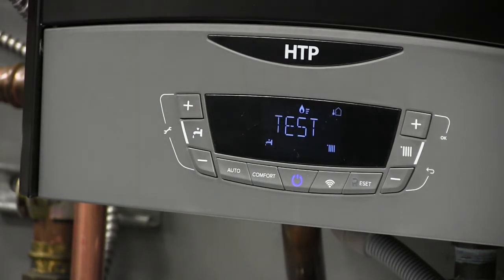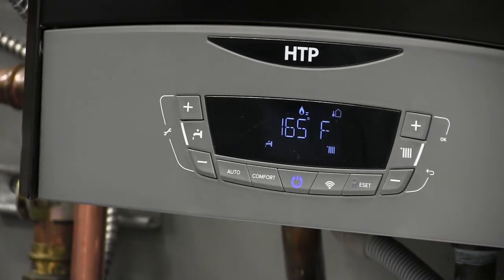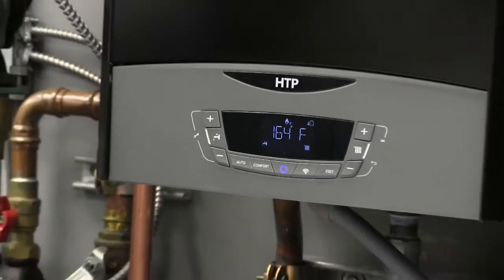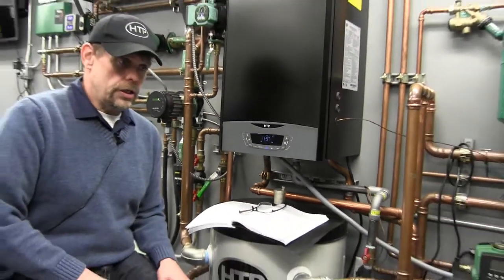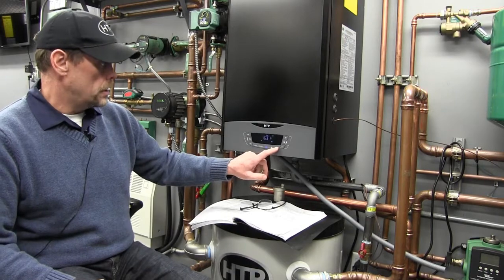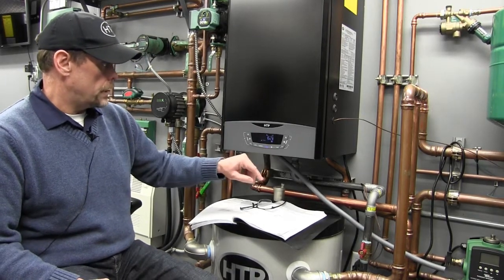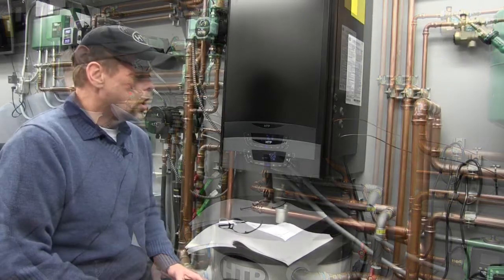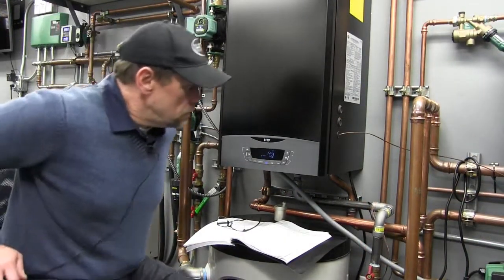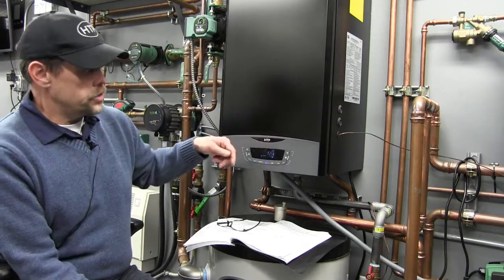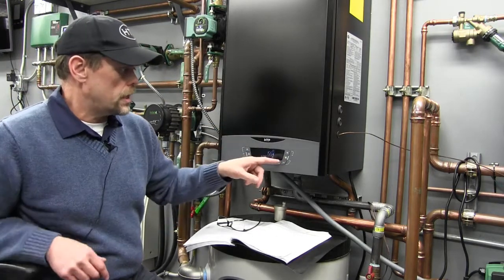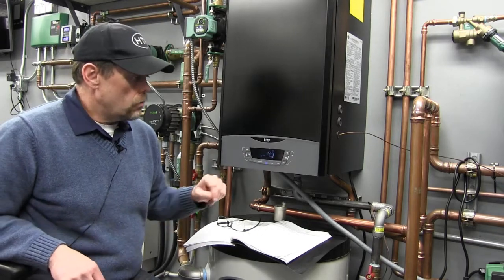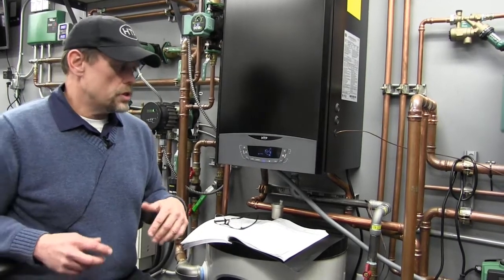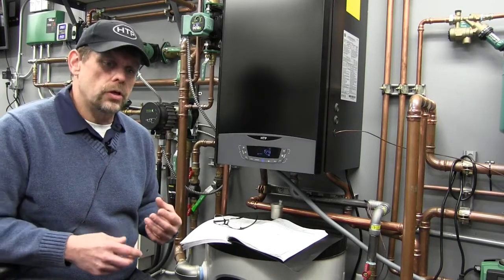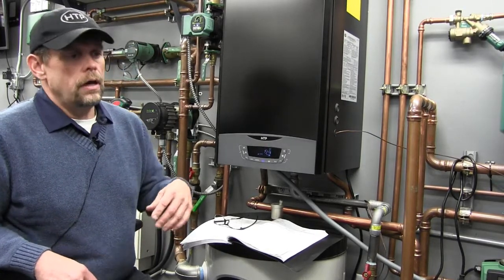So that is how we are going to get into our test mode. And if we're satisfied with our readings and/or we've completed our adjustments, we can go ahead, hit the reset button, and that will put us back into our run mode. Okay, the last 2 buttons on the right are the plus and minus buttons here on the central heating side, as indicated by the radiator icon. Now, this is going to function in a couple of different ways, and it depends on what mode we're in. In other words, if I'm in a set point operation or outdoor reset.